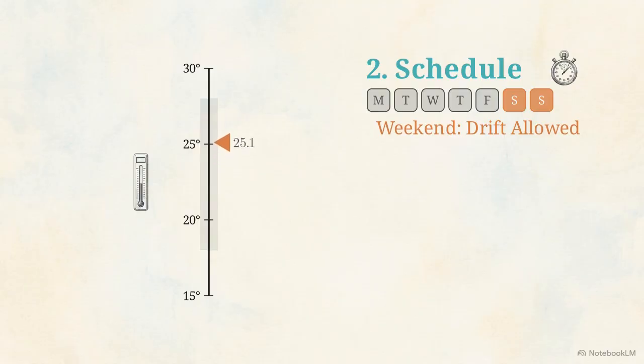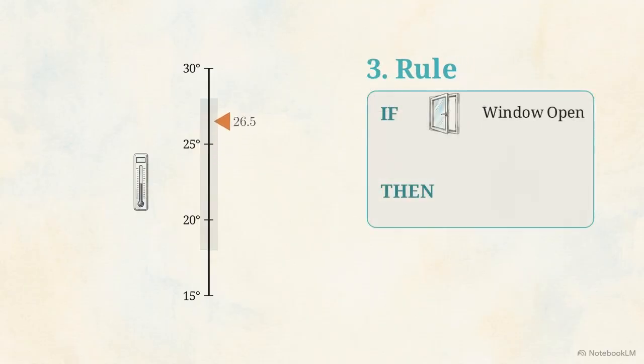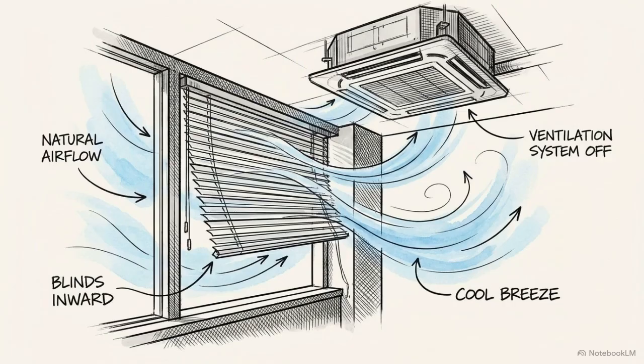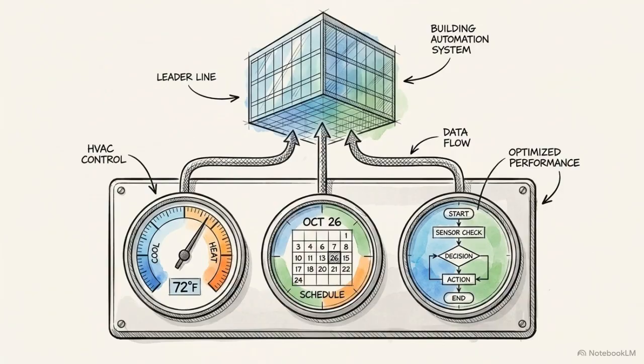The final boundary is a rule. This is conditional logic that overrides standard schedules when unusual physical events occur, like shutting off the cooling if someone opens a window. Set points provide the numerical target, schedules establish the daily rhythm, and rules provide the intelligence to break that schedule when reality demands it.